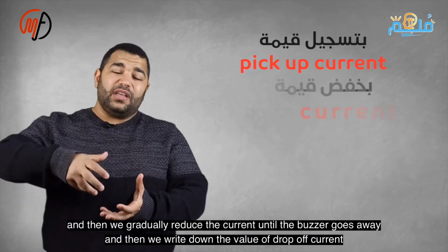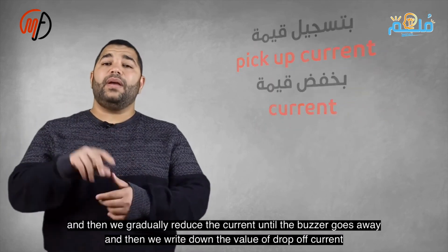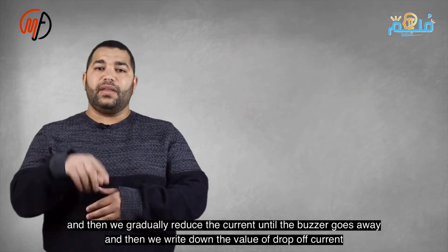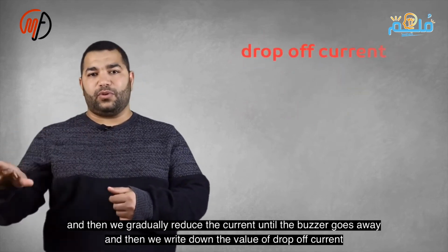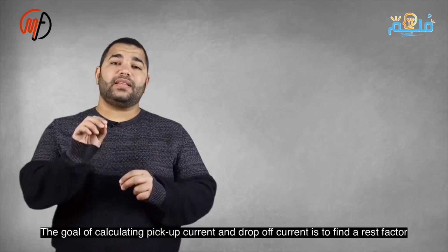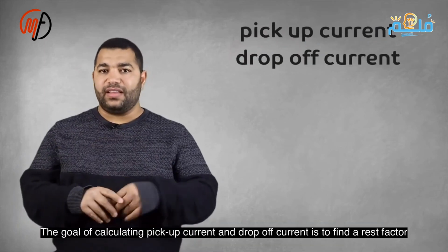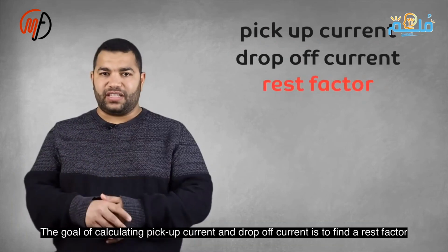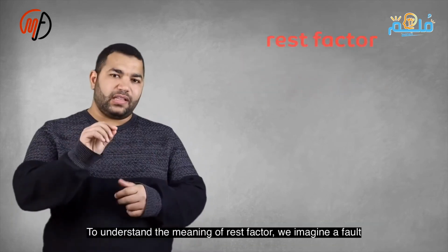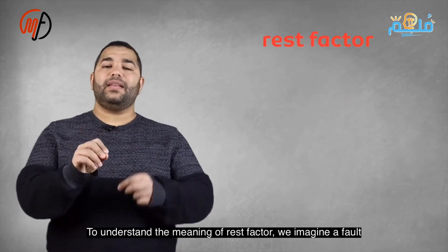A fault can cause the current to exceed a specified value, triggering the relay's timer to issue a trip signal. If the fault is transient, the current drops before activation and the relay reverses its decision. To measure response speed, we calculate the reset factor, the drop-off current divided by the pickup current, which is less than 1. A reset factor closer to 1 indicates a more sensitive relay.